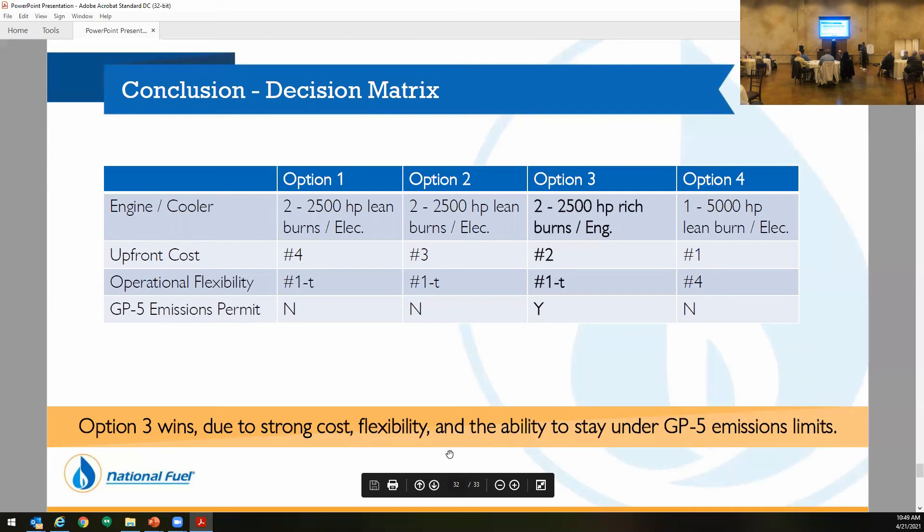After going through that, we did a rating system of the main three categories. Up-front cost — the 5,000 horsepower was a no-brainer, it was a lot cheaper. Operational flexibility — options one, two, and three give you the flexibility: if one unit goes down you can shut one down during maintenance and still have half the flow. Option four — if you shut that unit down, you're losing all your flow. And last but not least, the GP5 emissions permit. When we went through the study, the only option that was going to keep us under GP5 was the 2,500 horsepower rich burn units. We decided to go with that, just based on where everything's going with permitting — it gives us the flexibility. We're out of room on the pad, but if we expand the site, we could still be under GP5 by adding another couple of rich burn engines.